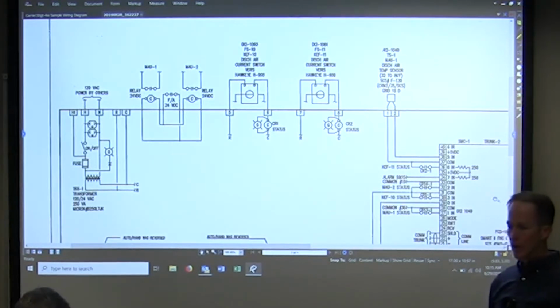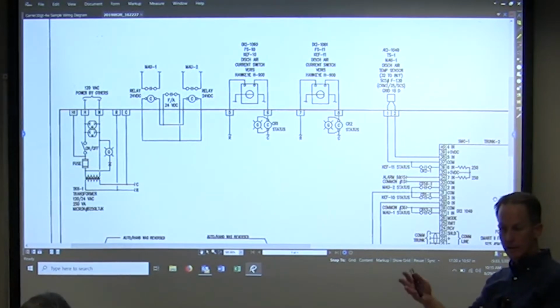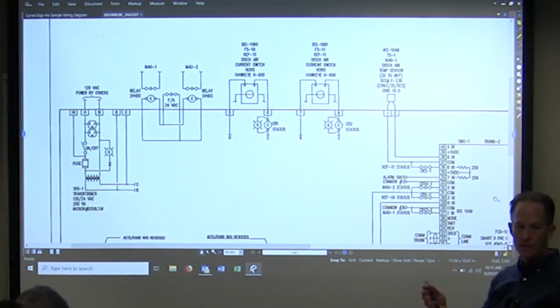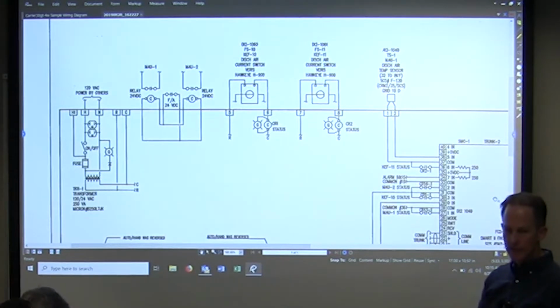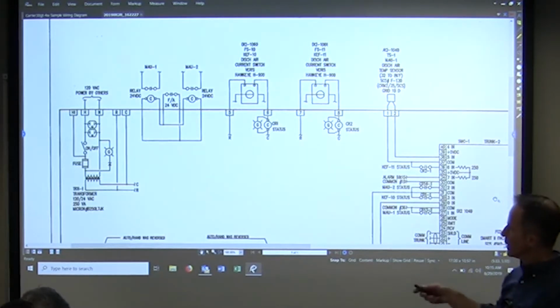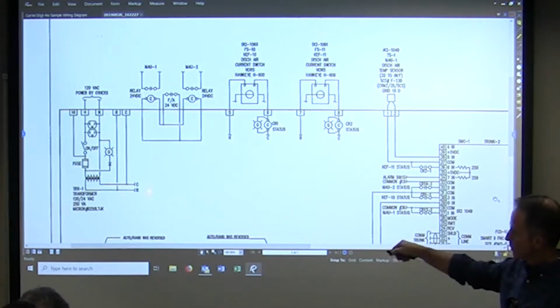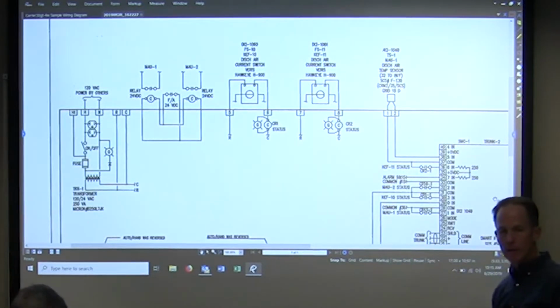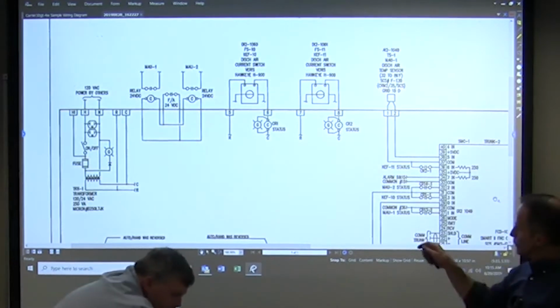Okay, so I heard 110 and 24, but I don't know what that means. 110, okay, 120 coming in, going to a transformer, 24 volts DC or AC? AC. Okay, all right. So we're 24 AC, and that's our R and C, typically how we label. 24 high is R, 24 low is common or C. Okay. So we have R and C.